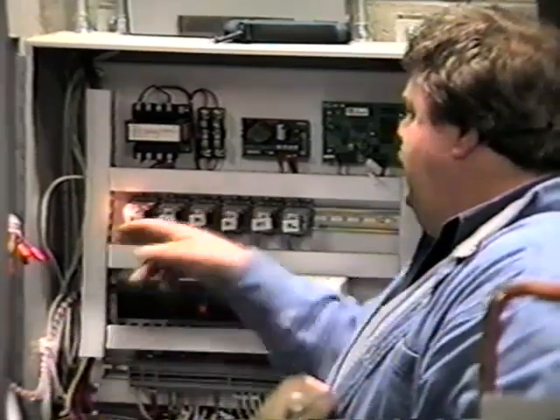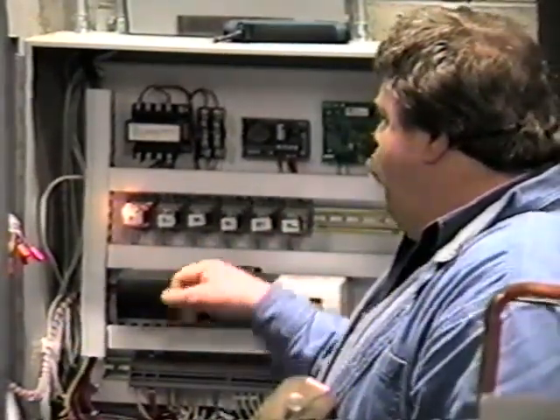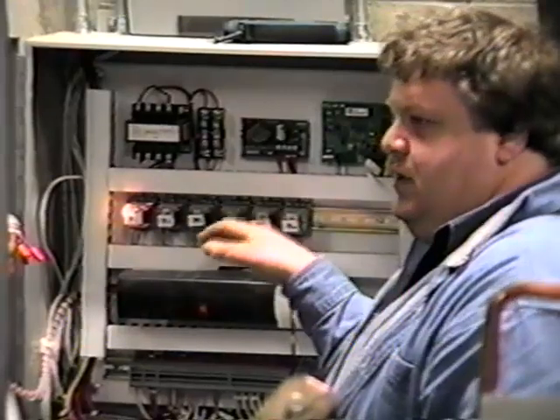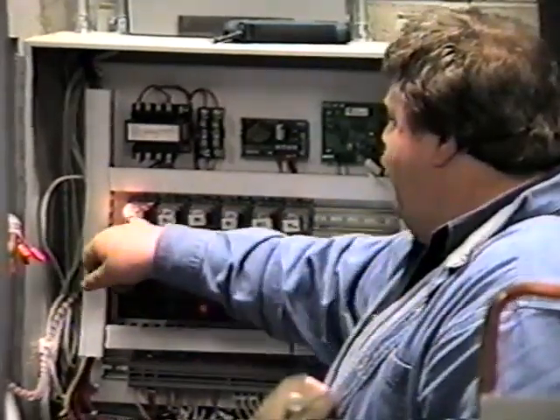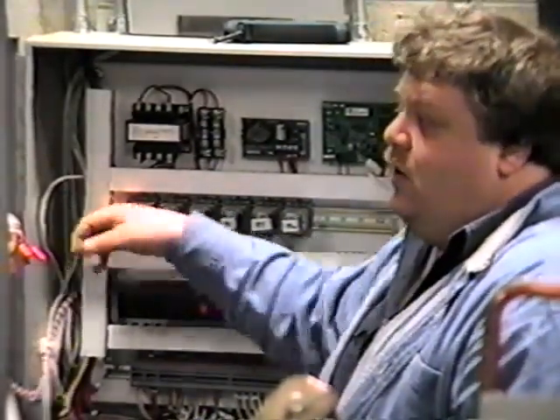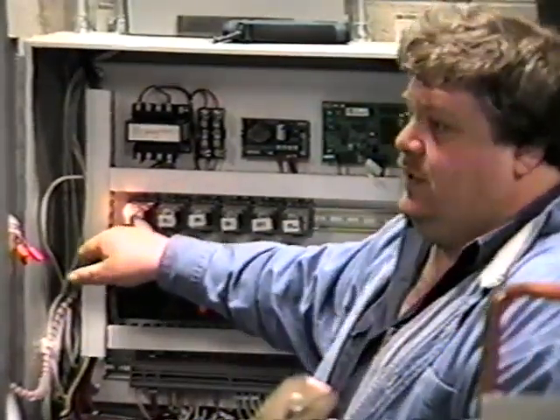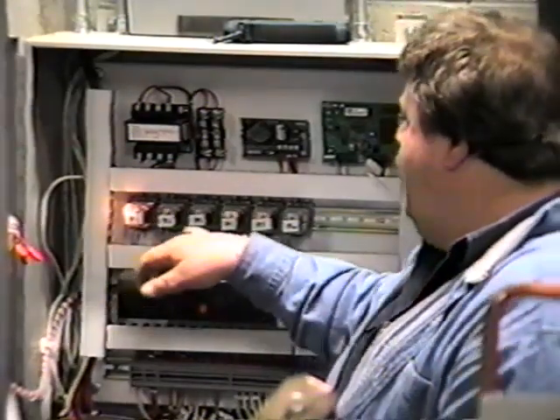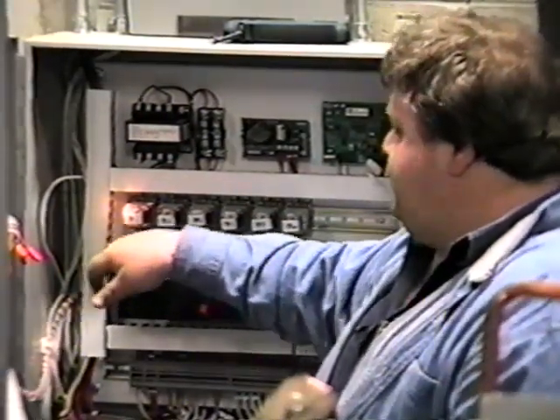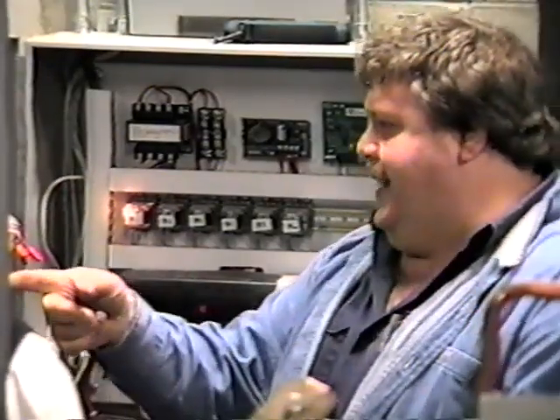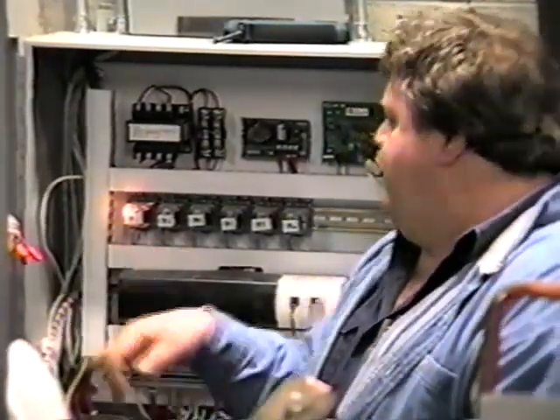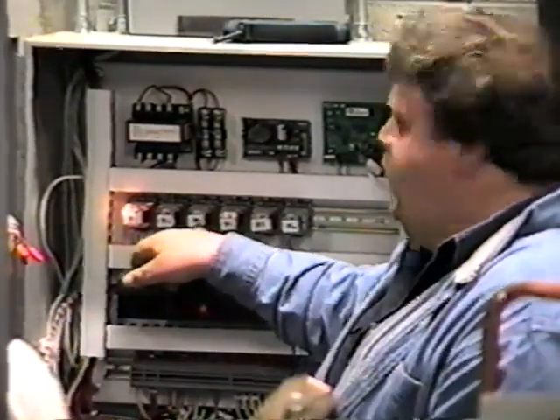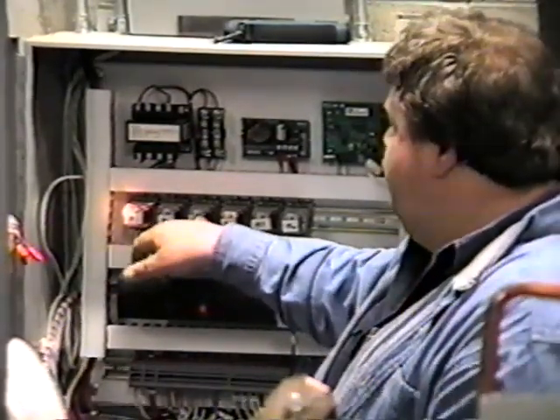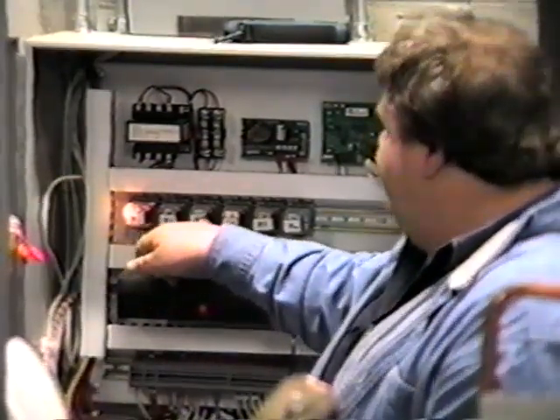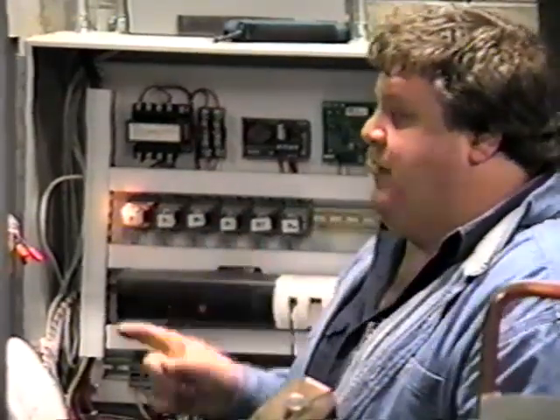So you're going to see, again with the paperwork, that each of these relays is a device. I know for one, relay one is our chilled water pump, and when this is lit, it should be at high speed. Once that's proven, there's a readback from that on the contactors that will allow the chiller to come on. I have to know that's number 3. So you'll see anything that should be on. If the light's on, you know something's supposed to be functioning.